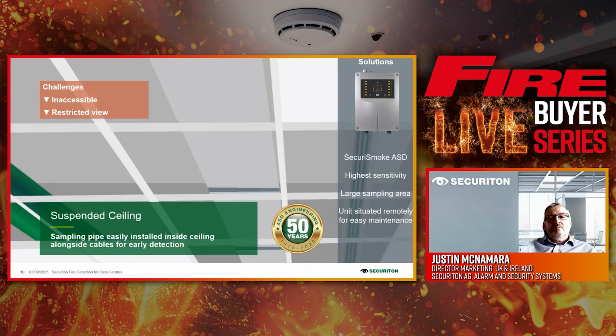Rather than look at point-type smoke detectors in these areas, aspirating smoke detection (ASD) is a great solution. It solves the problem of detecting within high airflow, but also makes maintenance much easier. Trying to access a ceiling void to maintain point detectors is tricky, cumbersome, intrusive, and expensive, to say the least. Aspirating can be a great solution in a suspended ceiling.